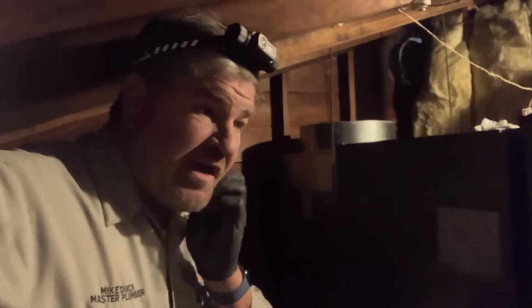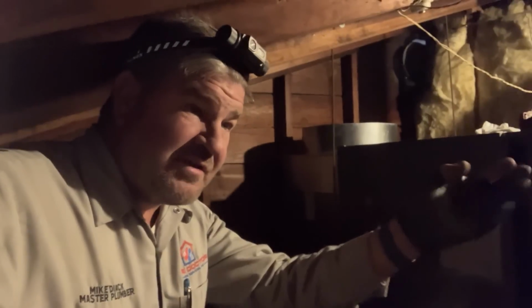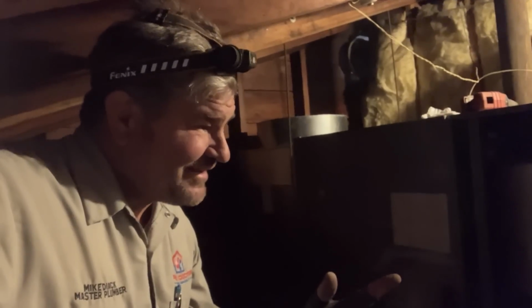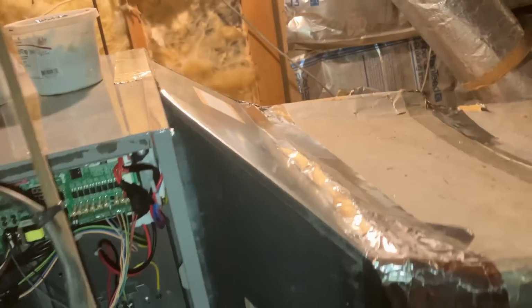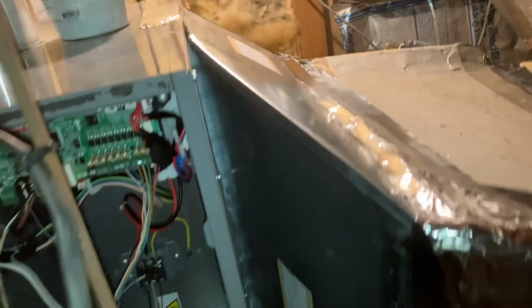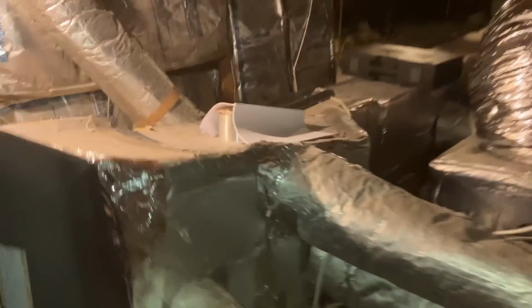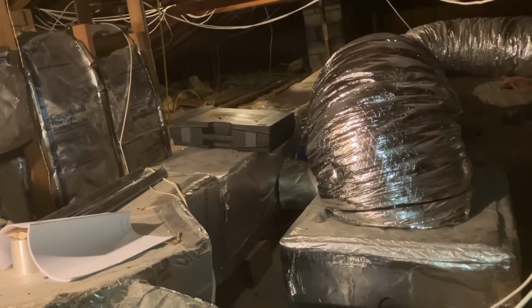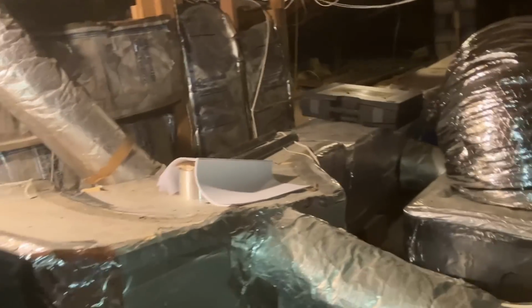We are going to size up all the ductwork and replace all the ductboard with a custom fabricated main plenum. And then we'll have flexible connectors that don't exceed 25 feet on each run for each branch off that main plenum. Because what I have here, while it is okay for most, and we did make this special transition piece to go from our supply side of the air handler to our ductboard, this ductboard is falling apart. I just can't keep this. And I gave the homeowner an attractive price to replace it. So we're good there.